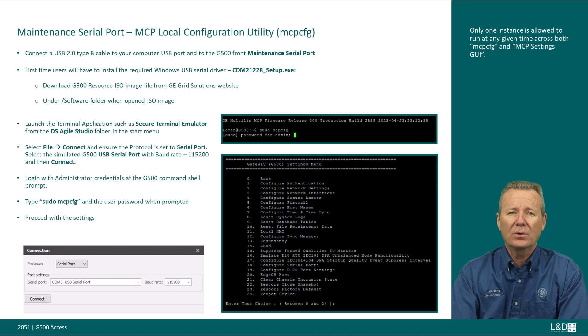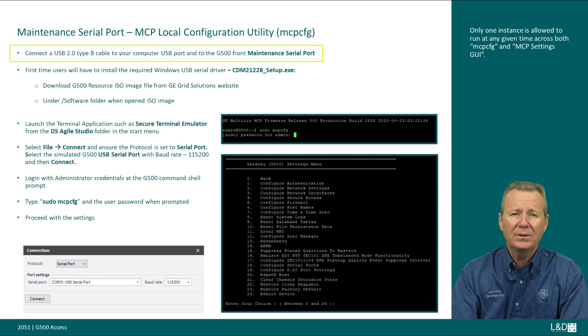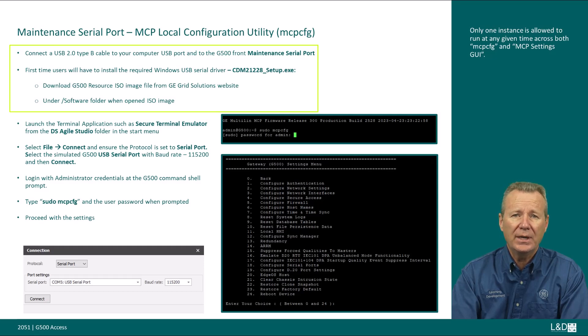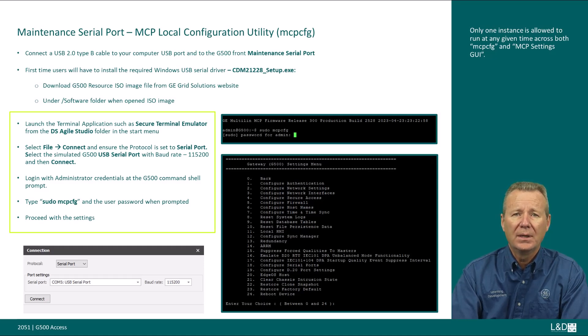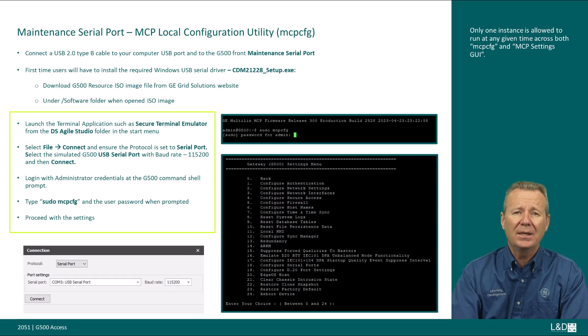The MCP Gateway local configuration utility can be launched locally via the front USB console port. Connect the USB 2 type B cable to your computer USB port and to the G500 front maintenance serial port. First-time users will have to install the required Windows USB serial driver, cdm21228-setup.exe. You can download the G500 resource ISO image from the GE Grid Solutions website and find the driver under the software folder when opening the ISO image. Launch a terminal application such as Secure Terminal Emulator from the DS Agile Studio folder in the Start menu. Select File, Connect, and ensure the protocol is set to Serial Port. Select the G500 USB serial port with baud rate 115200 and connect. Log in with administrator credentials, type sudo mcpcfg and enter the user password when prompted, then proceed with the settings.